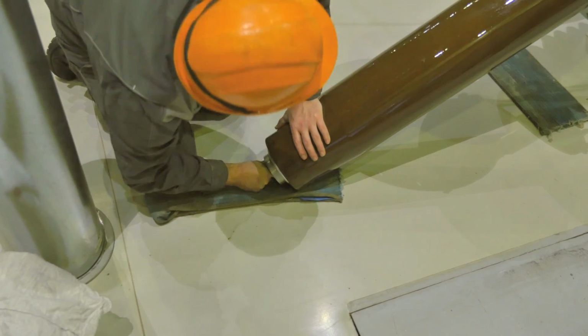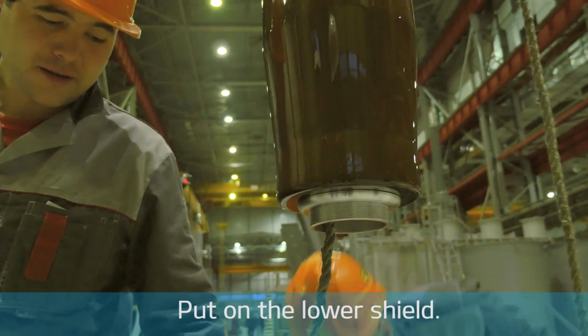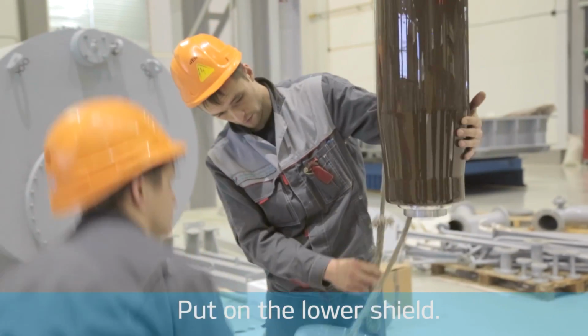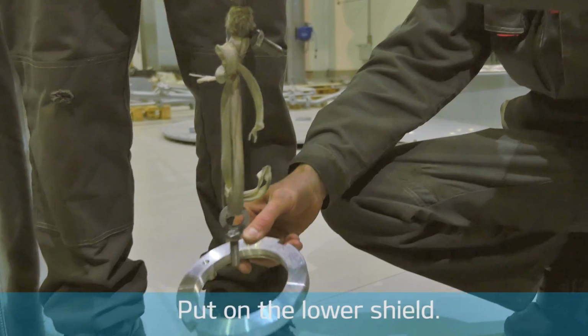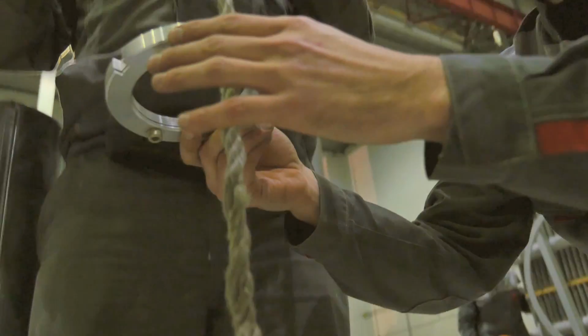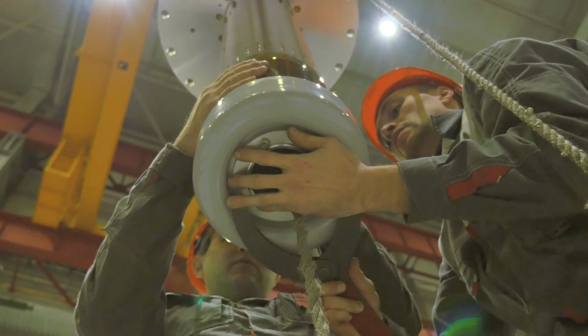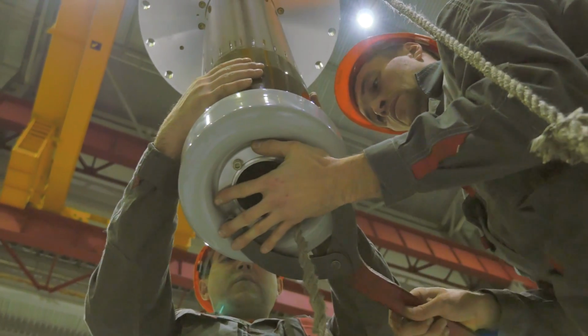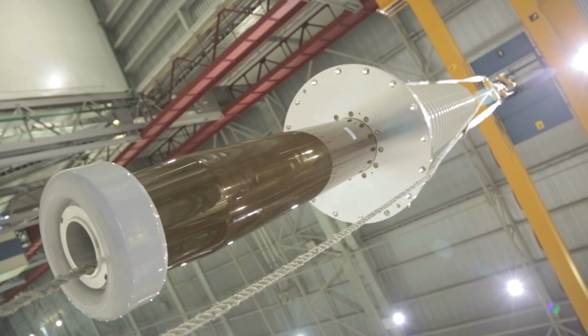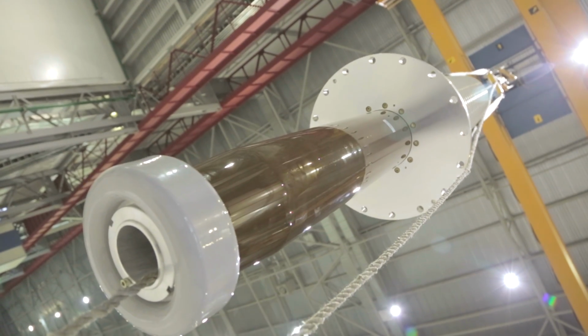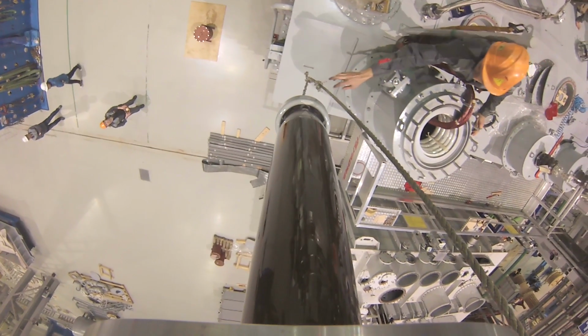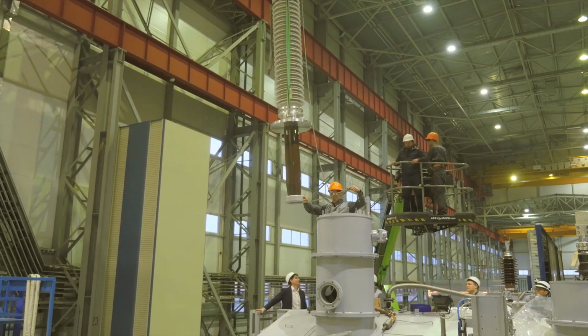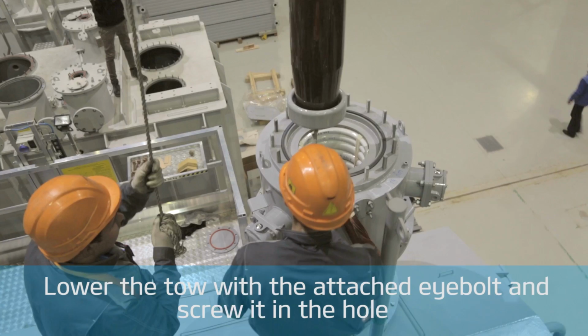After the bushing is set to a vertical position, put on the lower shield. It is fixed by a special split nut, which should be screwed tight on the thread segment of the tube until stop at the shield. The nut should be then fixed with a supplied bolt to avoid unscrewing. Upon completion of those operations, one can proceed to the bushing installation in a transformer.